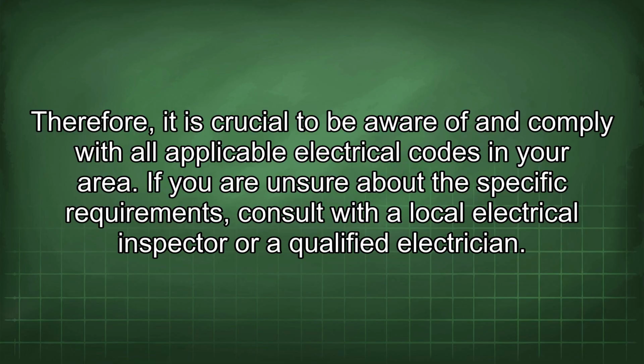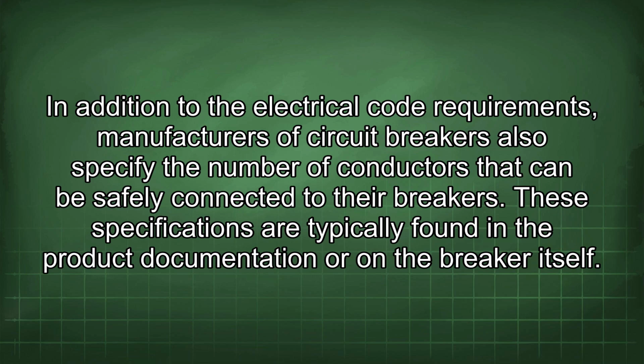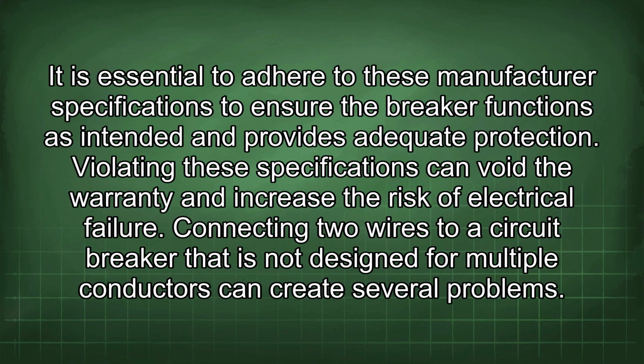If you are unsure about the specific requirements, consult with a local electrical inspector or a qualified electrician. In addition to the electrical code requirements, manufacturers of circuit breakers also specify the number of conductors that can be safely connected to their breakers. These specifications are typically found in the product documentation or on the breaker itself. It is essential to adhere to these manufacturer specifications to ensure the breaker functions as intended and provides adequate protection. Violating these specifications can void the warranty and increase the risk of electrical failure.